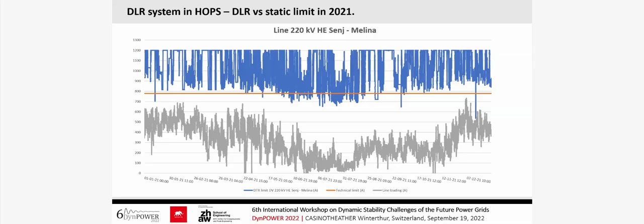You can see that most of the time during the year, you have a much higher limit than the static one. That's because the static limit is made for summer conditions, with 40 degrees outside and very slow wind, but that's not the case most of the time.